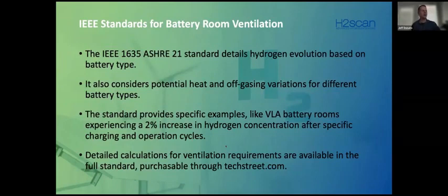So as I mentioned before, I actually sit on the IEEE committees for the stationary batteries. And we are just now beginning to rewrite IEEE 1635, which is a joint standard with ASHRAE. So that's IEEE 1635 ASHRAE 21. It details the hydrogen evolution based on the battery type. There's a calculator being developed with all the different battery manufacturers' models of batteries. You can add the room size and some of the characteristics of the site as well as the battery type, and it'll calculate what the hydrogen evolution will be for that battery type and how much ventilation you really need in a given room.